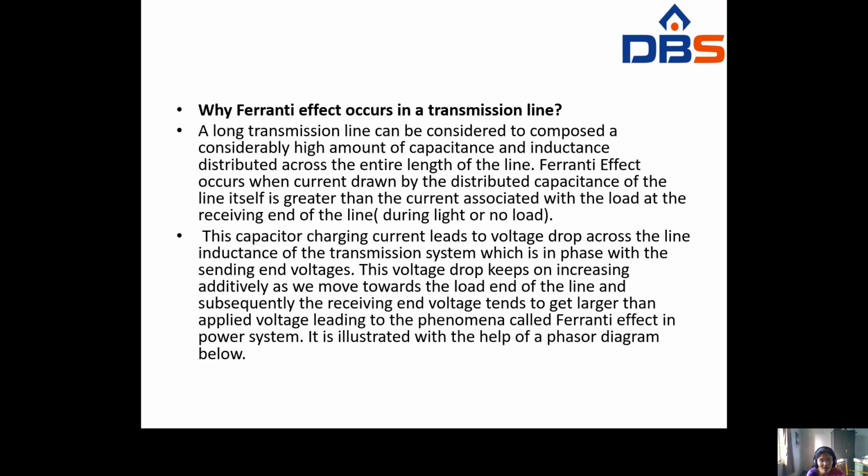This voltage drop keeps on increasing additively as we move towards the load end of the line. The voltage drop increases at the end of the line, and subsequently the receiving end voltage tends to get larger than the applied sending end voltage. This phenomenon is called the Ferranti effect in power systems.